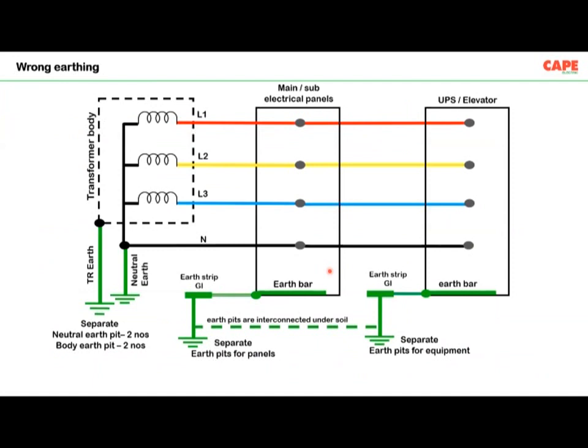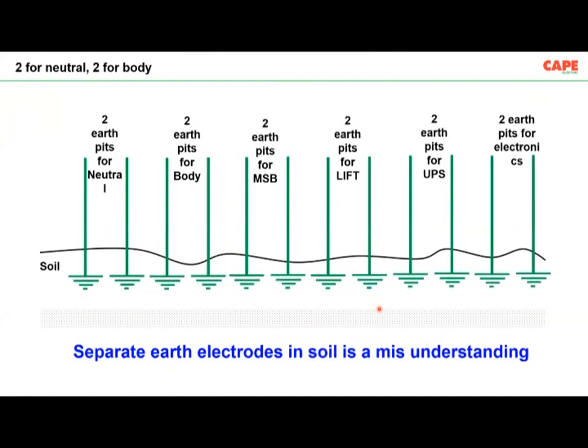Now, but what do we do actually? In most of the installations in India, the transformer neutral has two connections to two earth pits in soil. Transformer body, two separate. Panel board, two separate. UPS, two separate. Elevator, two separate. So this is basically a kind of undefined network. Separate, separate, separate, separate earth pits. So basically, this is an undefined earthing. If you make this kind of earthing, you can never achieve safety. So this is absolutely wrong.